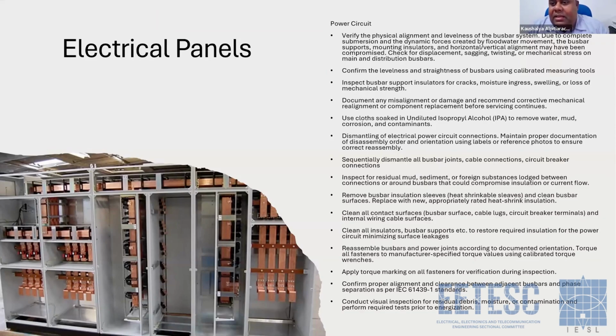Use a well soaked cloth and clean with isopropyl to remove water, mud, corrosion, and all the contaminations. All the areas you may need to inspect for oxidation, and you may need to sometimes file where the oxidation has happened. Thereafter, you can clean and apply any sort of heat shrink tubing as necessary, and can reapply.